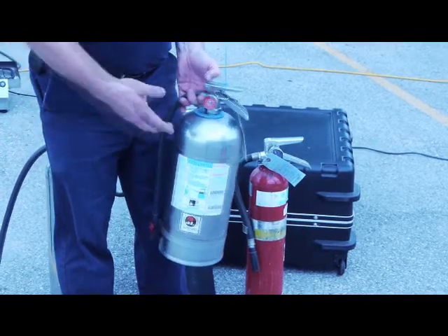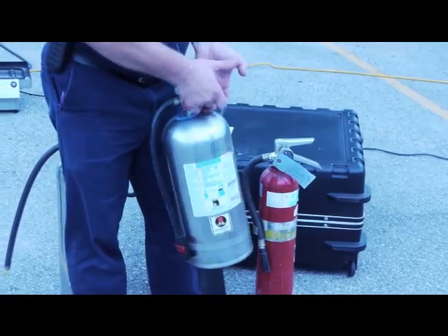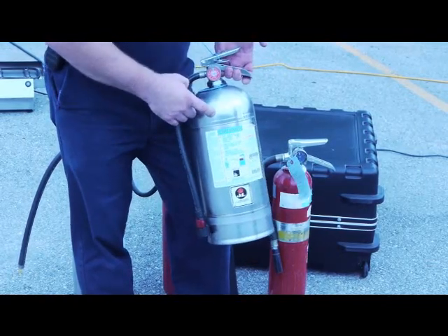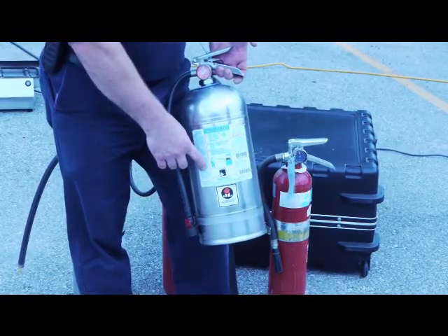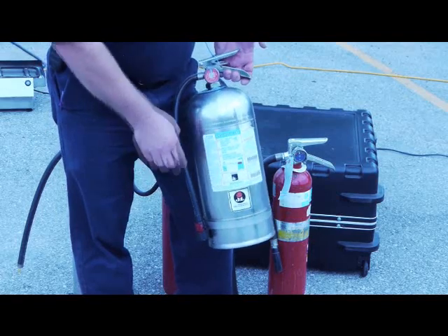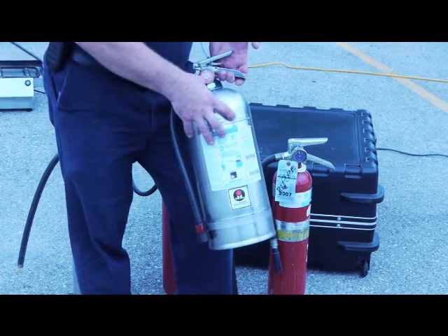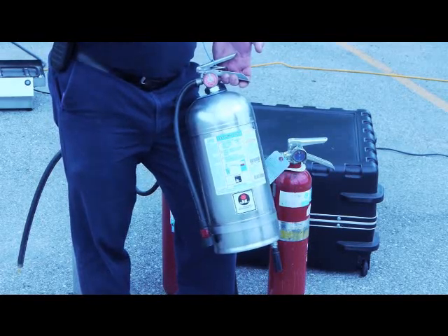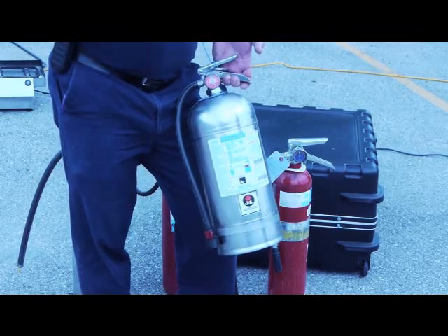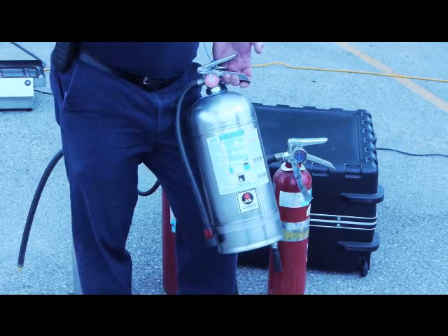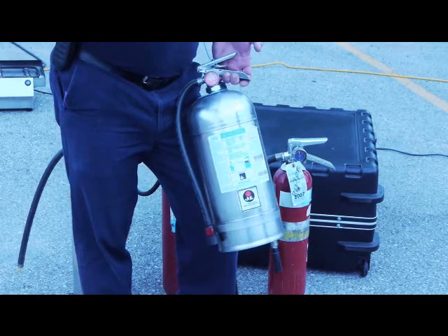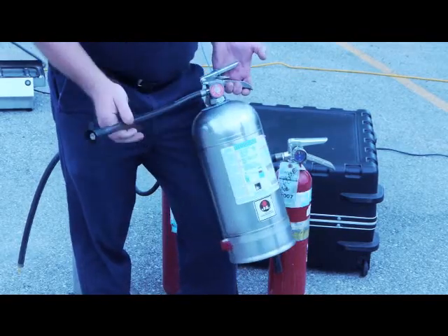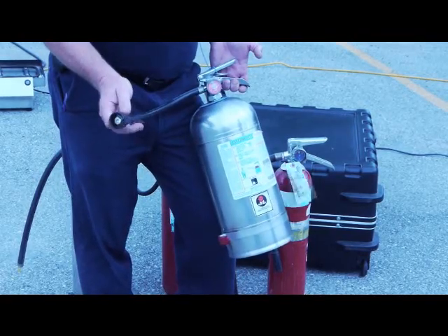That will be specific to the location you're at, and any supervisors or people in that area will know what you have. This extinguisher is for Class K fires, kitchen cooking oils only. This is not to be used on the initial fire. The system is designed so that when a fryer or grill is on fire, you pull the overhead hood and duct system. That extinguishing agent does the bulk of the work, and if there's anything else you need to do in addition, you can grab this portable extinguisher to help finish off putting out the fire.